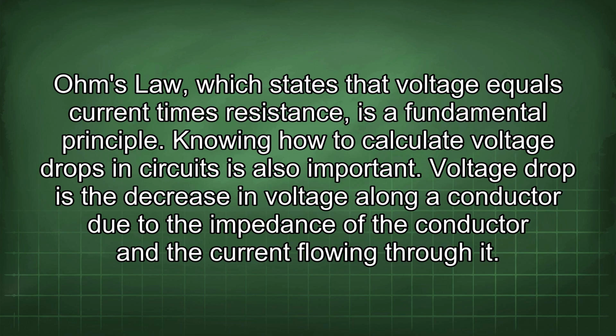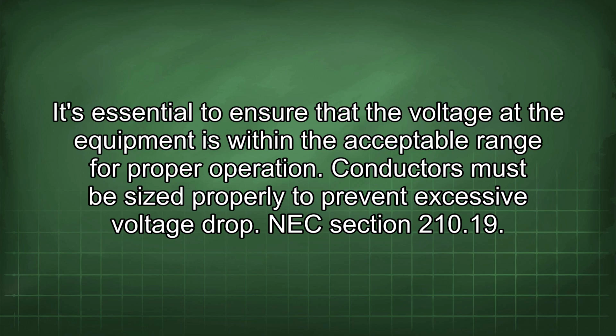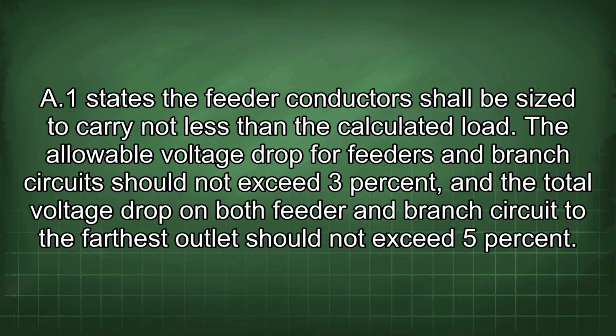Voltage drop is the decrease in voltage along a conductor due to the impedance of the conductor and the current flowing through it. It's essential to ensure that the voltage at the equipment is within the acceptable range for proper operation. Conductors must be sized properly to prevent excessive voltage drop. NEC Section 210.19(A)(1) states the feeder conductors shall be sized to carry not less than the calculated load. The allowable voltage drop for feeders and branch circuits should not exceed 3%, and the total voltage drop on both feeder and branch circuit to the farthest outlet should not exceed 5%.